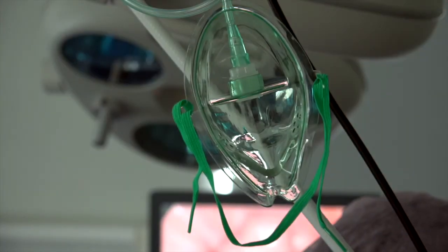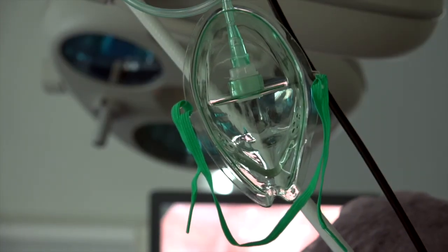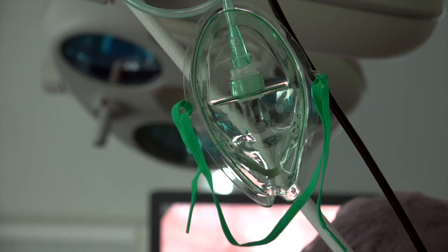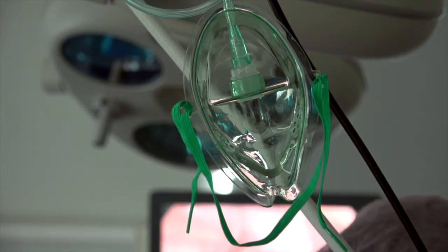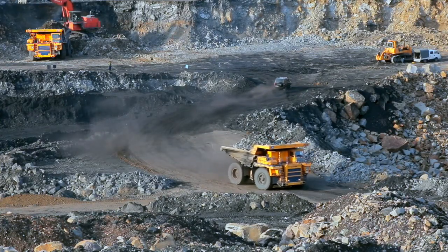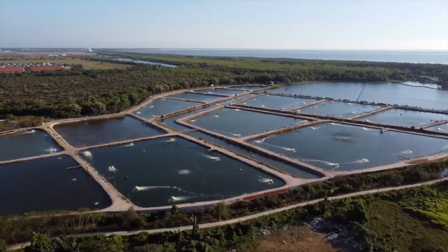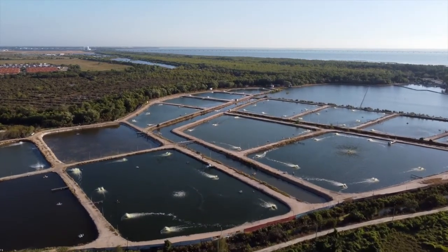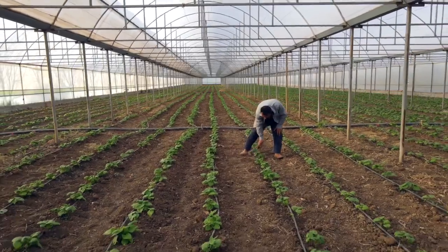Unless the industry or application requires an oxygen percentage higher than 95%, acquiring a higher oxygen purity will typically not pay dividends. Oxygen 93 is an industry standard and is perfectly adequate to provide the necessary amount of concentrated oxygen to the majority of industry applications.